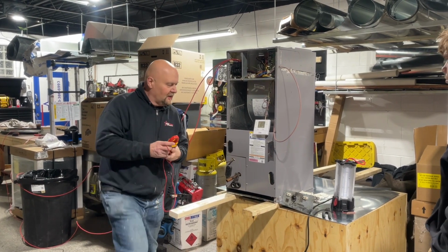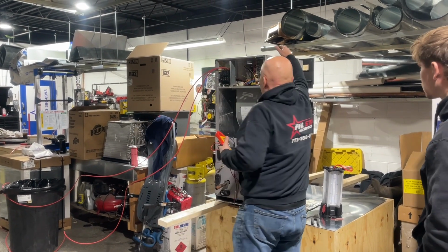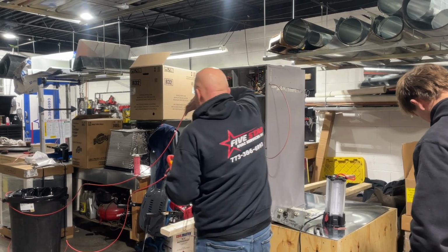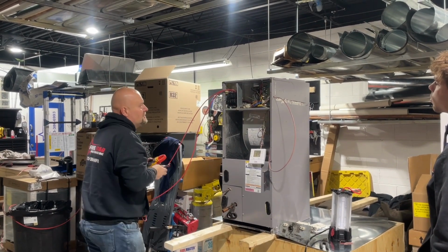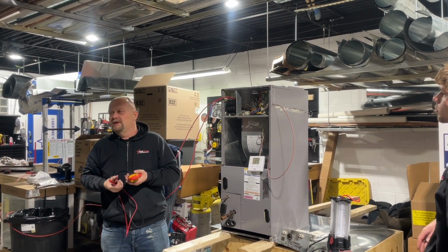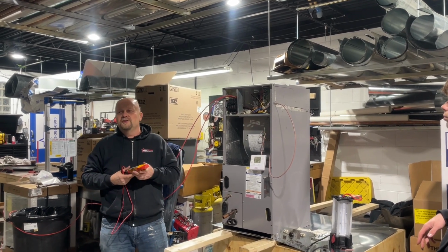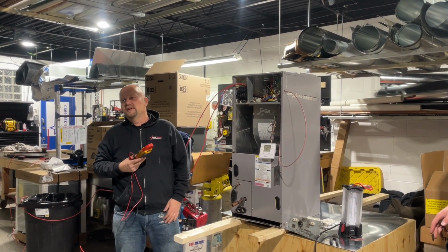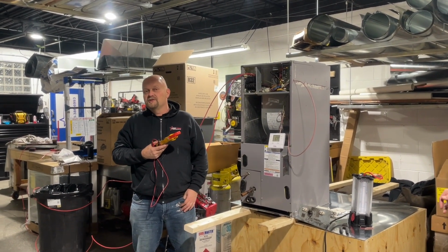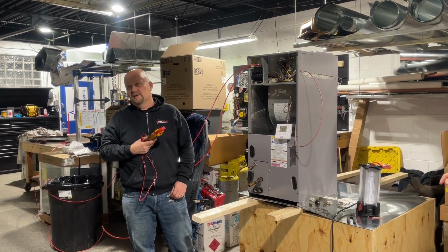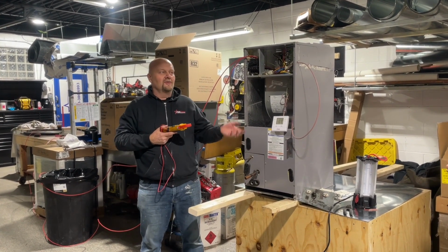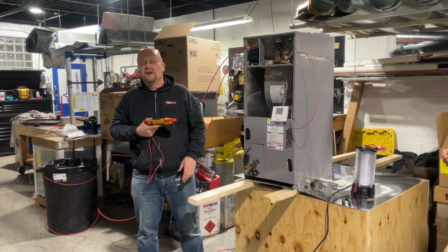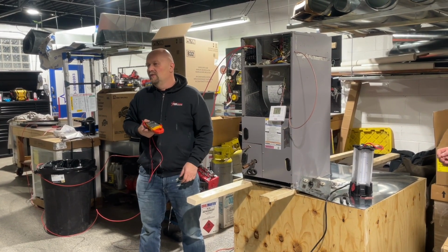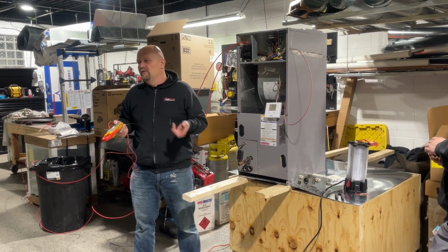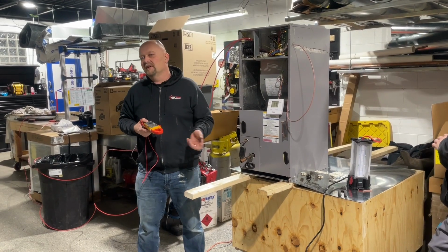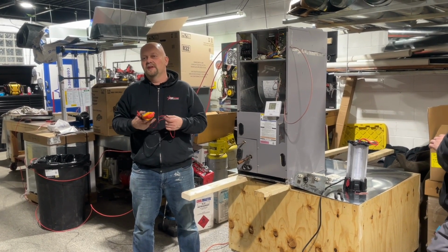I mean, obviously we can check now to make sure we have warm air coming at the top and it's warm. Also, typically, the air discharge on the electric furnace is much cooler than a normal furnace. You're looking to get at most 130 degree discharge of air. Typically 110 is what you're gonna have, unless you have a really, really oversized furnace and not enough ductwork, then you're definitely cooking the wires. 110 degrees is enough. When you're bringing in 60 to 70 degree air, you're gonna get a 40 delta T.